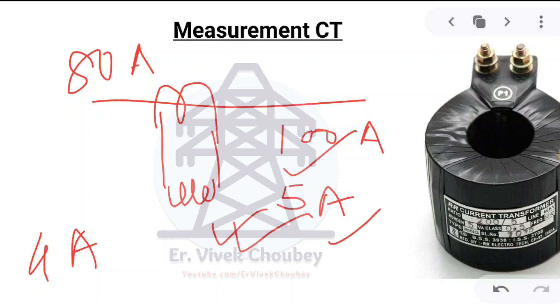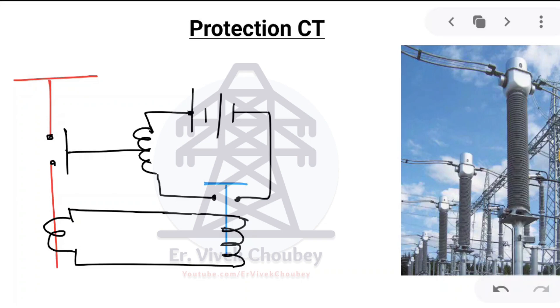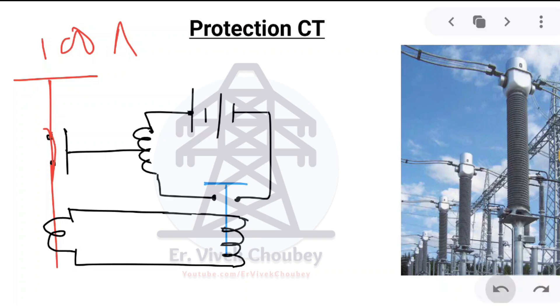Now let us come to the protection current transformer, which has an entirely different role to play. It is used to actuate a relay, which will then trip the circuit breaker. Let's say a line is carrying 100 amperes of current and suddenly some fault happens — a line-to-ground fault, line-to-line fault, or other types. The basic feature of a fault is that the line current increases 10 to 20 times, which is very normal during a fault. At that time, it is important that this line is disconnected so that the fault can be countered.